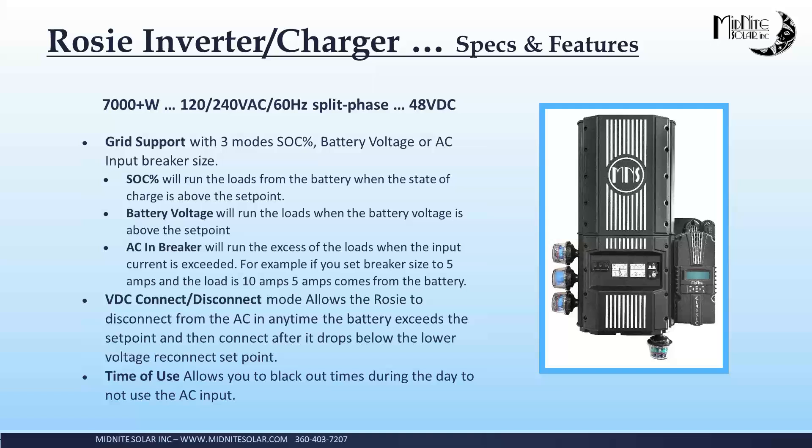You can also set it up for support based on the input breaker size. If you had an off-grid system with a 2,000-watt harbor freight inverter generator, you can set the Rosie to have an input breaker size limit, and if some big load comes onto the Rosie, it will draw the rest out of the battery and not overload the generator. Also, the Rosie will run from a single 120-volt input. If you had that harbor freight 2,000-watt inverter generator, the Rosie is putting out 120/240 — you can put 120 volts to L1 or L2, and it will charge the battery and make the other leg and still put out 240 volts for the load. The Rosie can also be set to 120 only out if you wanted to.